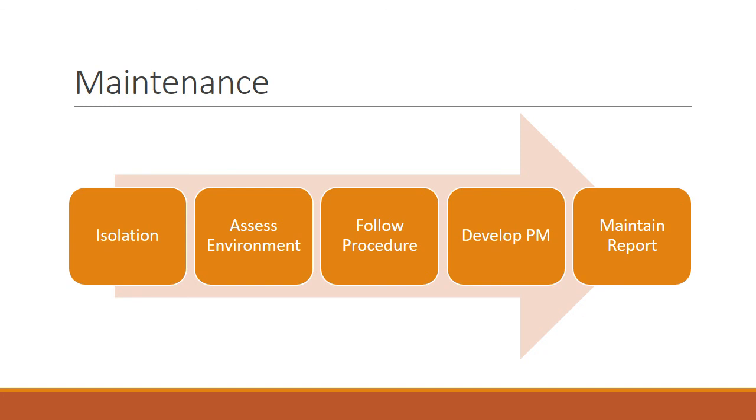Test of voltages using high-pot or megger testing, as well as if there are any electromechanical or digital relays being used within the switchgear. They should also be a part of the procedure to follow for testing or for your maintenance.